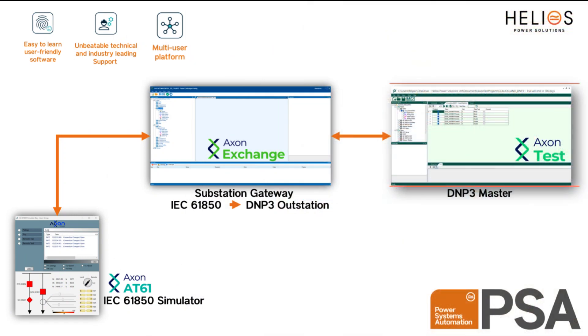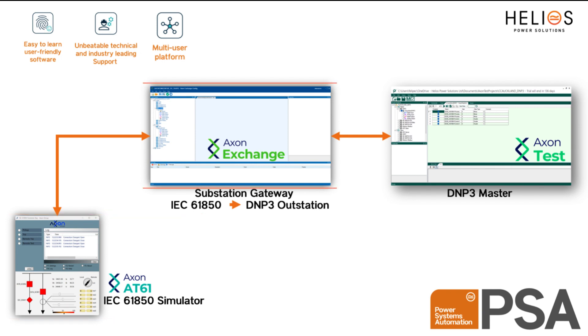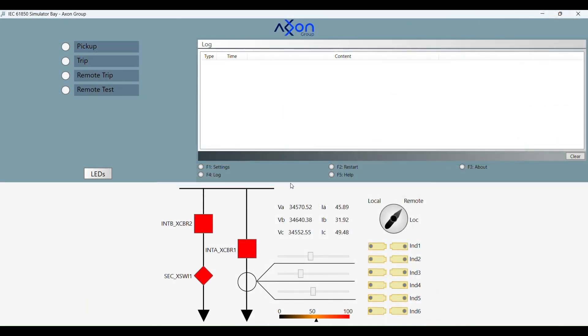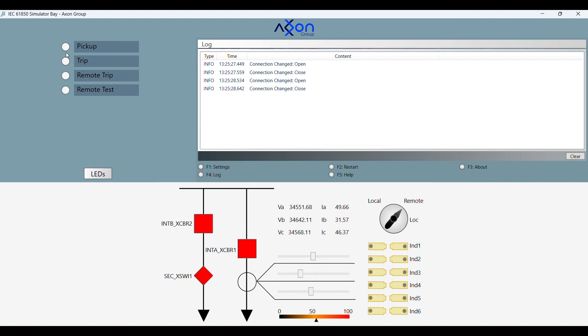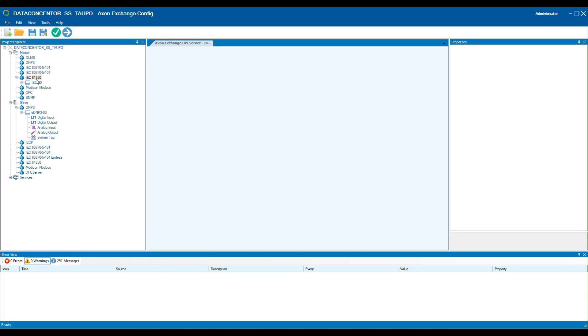In this test rig we will use the Axon products AT61 and Axon Exchange. The simulator bay tool in AT61 allows for simulating a relay with IEC 61850 communication, facilitating practice testing and learning exercises without requiring external hardware or CID files.